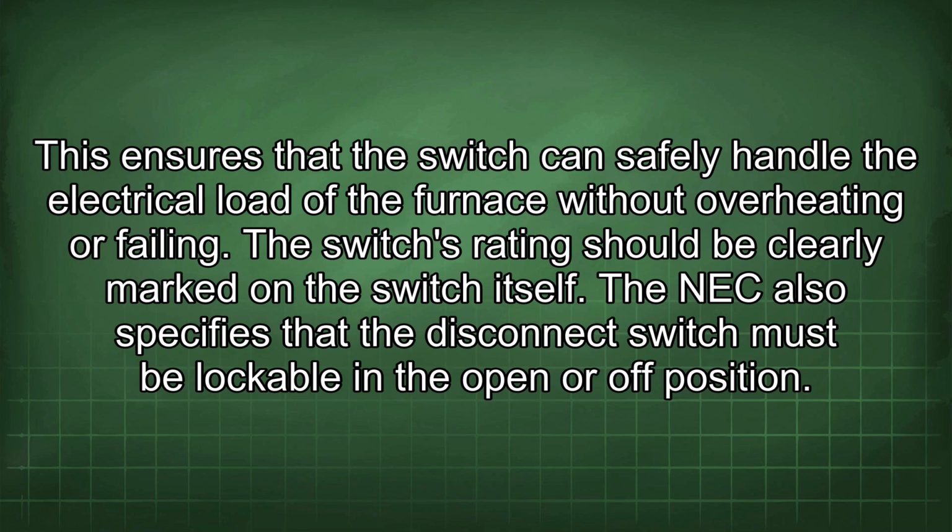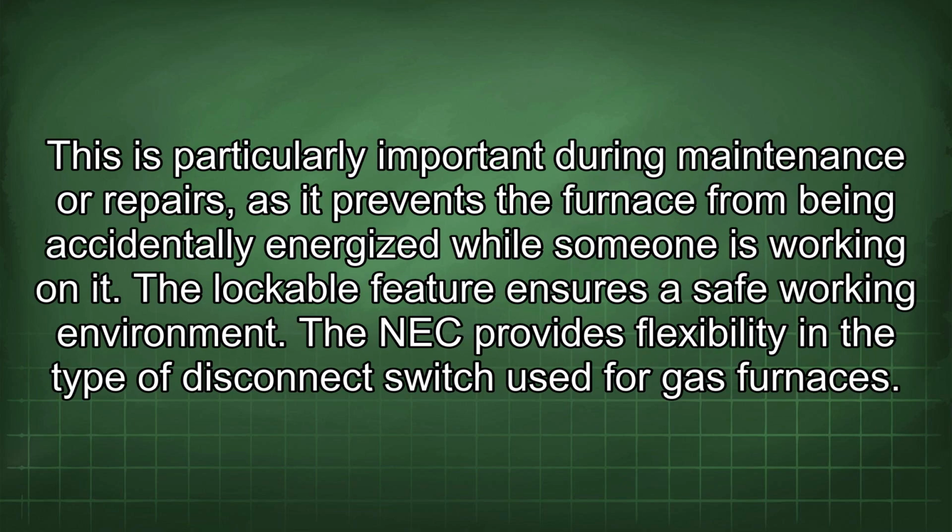The NEC also specifies that the disconnect switch must be lockable in the open or off position. This is particularly important during maintenance or repairs, as it prevents the furnace from being accidentally energized while someone is working on it. The lockable feature ensures a safe working environment.